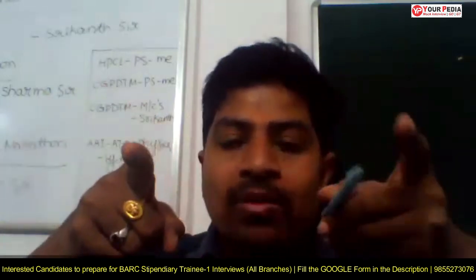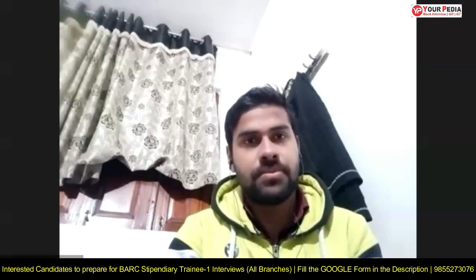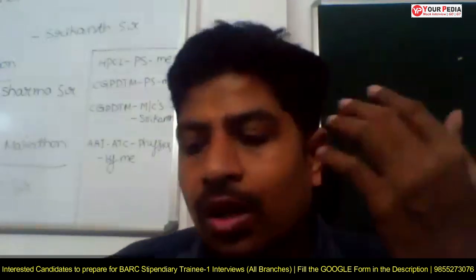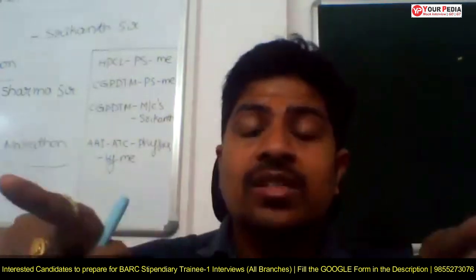The major disadvantage of corona is a short circuit. Suppose you take two power conductors, phase A and phase B, with air between them. If that air completely gets ionized, these two phases will directly get short circuited. That is a major disadvantage, but we are going to keep enough distance. The next major disadvantage of corona is power loss. So the main disadvantages of corona are power loss and short circuit. If you are not maintaining enough distance, then a short circuit is going to happen. Then how to decrease the corona?